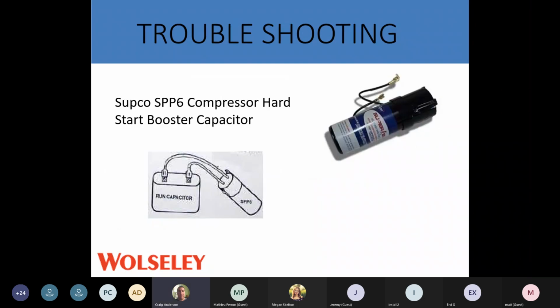This is a great thing to have in your truck. If you don't have one, it's a hard start kit. Beginning of the season, this compressor has not done anything for 6 or 7 months. It's sitting there, the unit's old. Sometimes it needs a little get up and go. If you get to a unit, the unit turns on, compressor turns on, then it clicks off. Let's try one of these. You can save the person a lot of money. Put it on. If it works, leave it on. Could give them another 2 or 3 years out of that compressor. It's just giving it a little get up and go to get moving. Great thing to have in your truck. They're like $35. They could save your customer a lot of money and save you a lot of time.